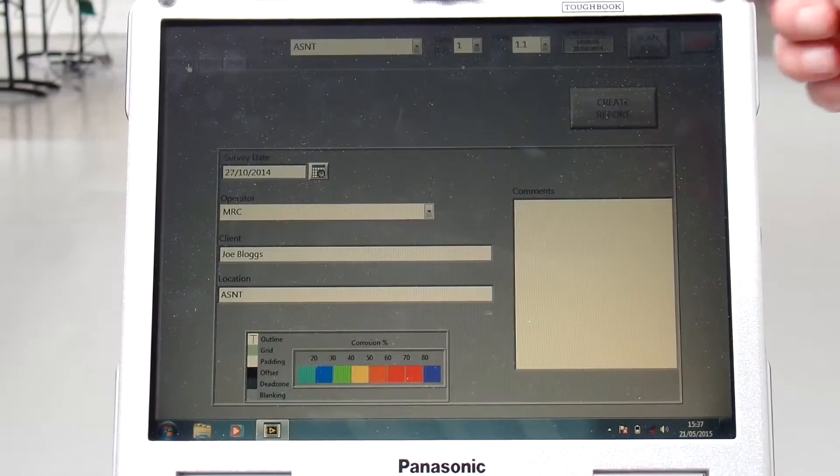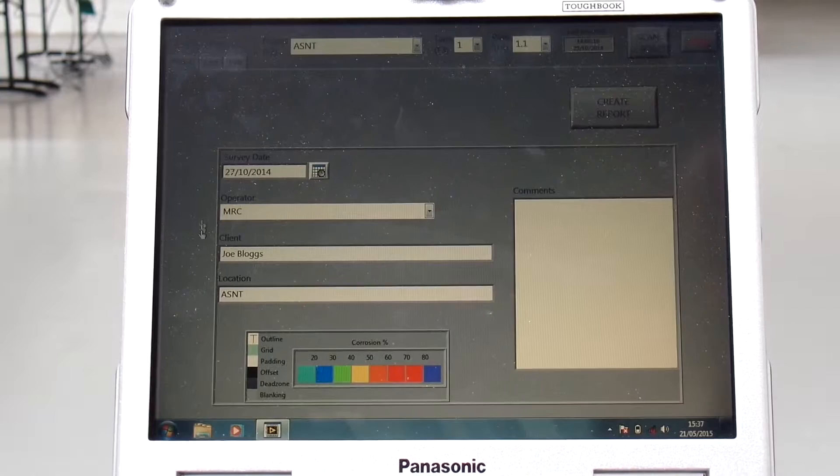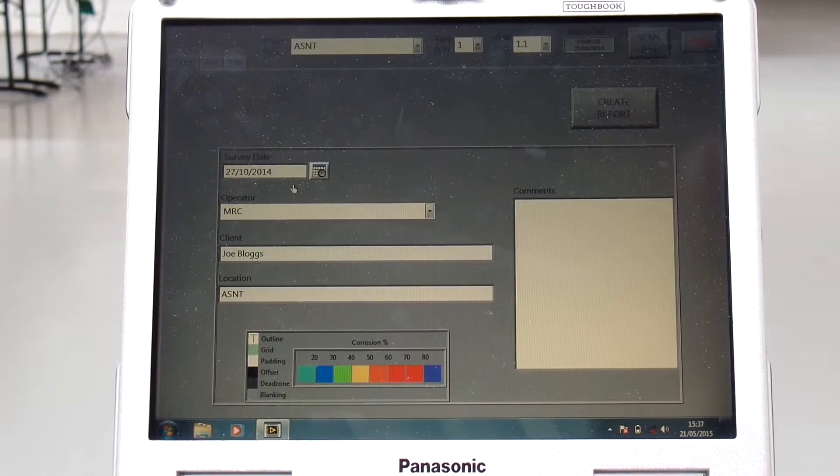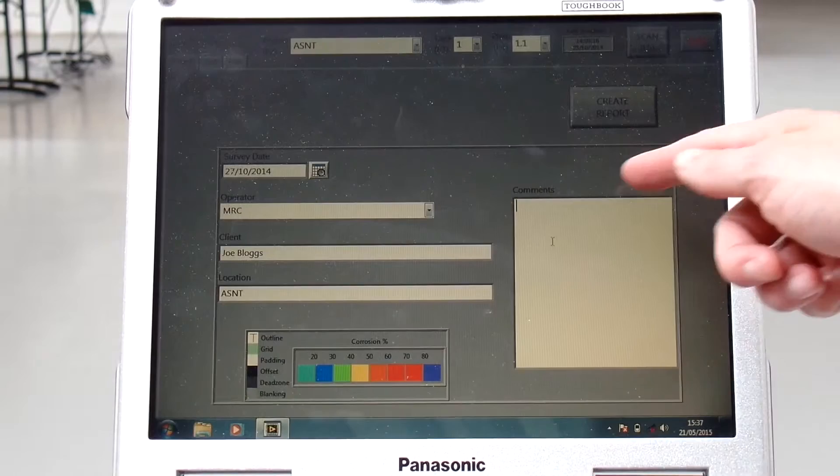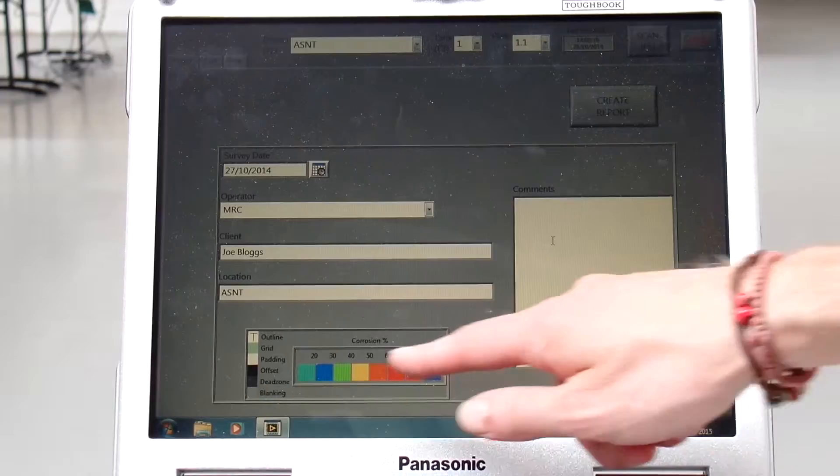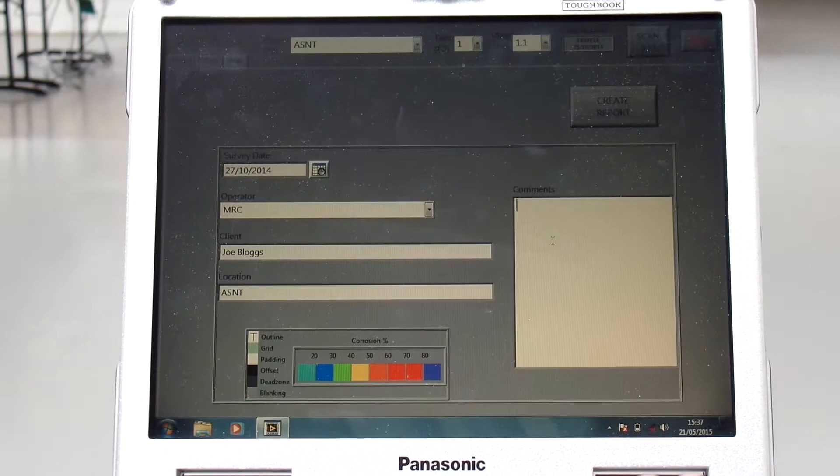The inspection software has three tabs: project, tank, and plate. The project tab allows for project information to be entered—the survey date when the inspection is being carried out, the operator name, the client, and the location of the tank that is to be inspected. Comments can be entered in the comments field. These are reproduced on the report at the end of the inspection. A color map, which is used to display colors in the C-scan corresponding to different through-wall thicknesses, is displayed here. This can be edited as required.